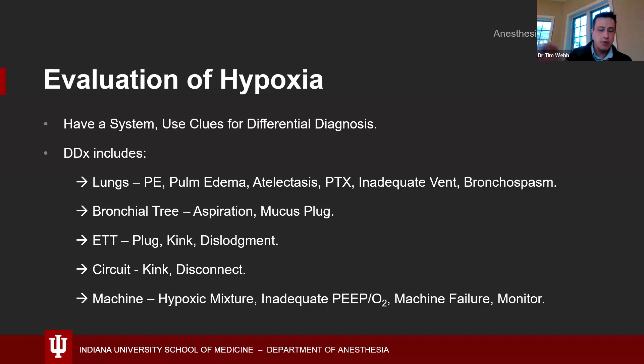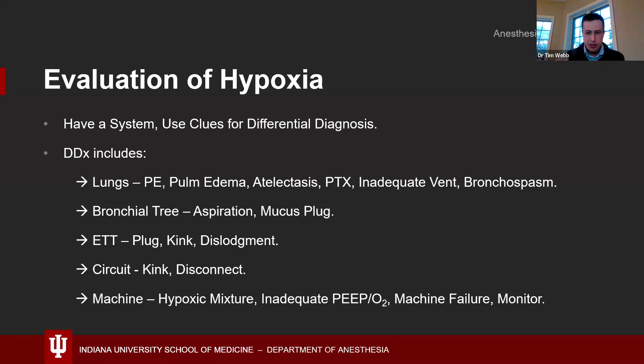Finally, I move all the way back to the machine. It seems unlikely, but there could be a hypoxic gas mixture, inadequate PEEP or O2 for the patient's condition, or even a machine failure. Usually the last thing I consider is whether the monitor itself isn't working — I make sure there aren't other issues going on before questioning whether it's the SAT probe.